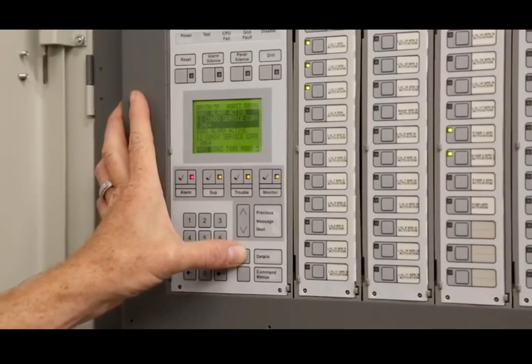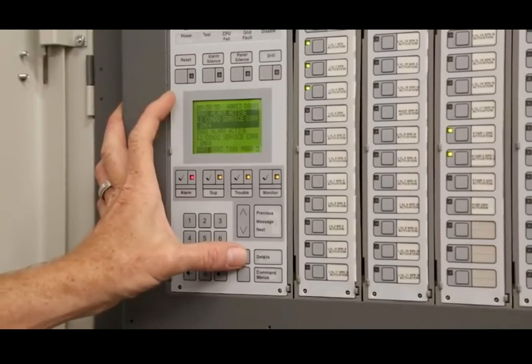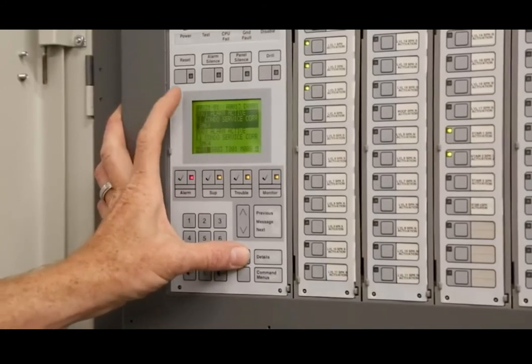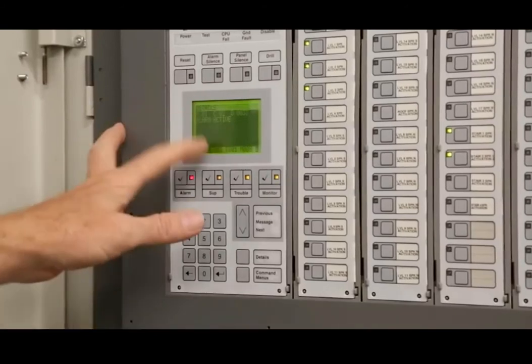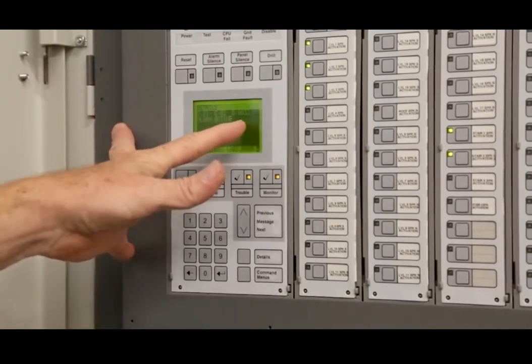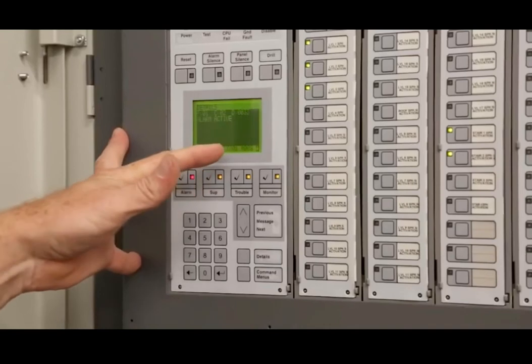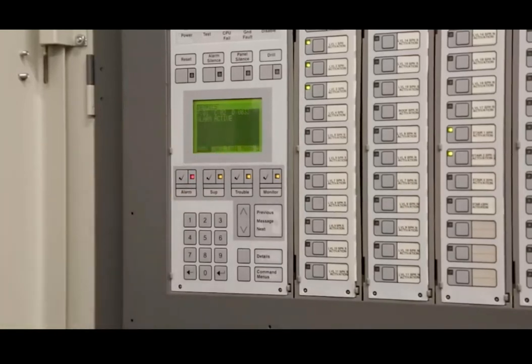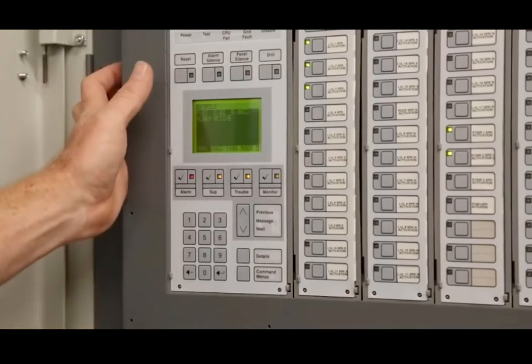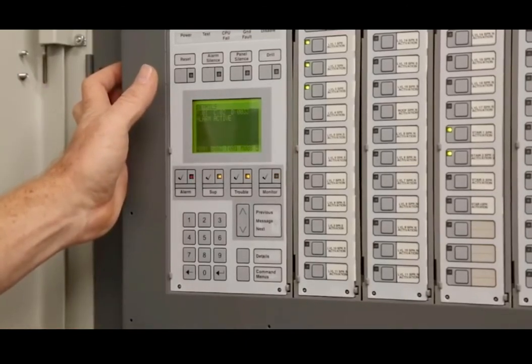If it's up higher and you can't actually see it and you see the number, remember I told you you can always go to details. Whatever's highlighted, we can go to that. So right now we know it's from panel 1, card 2, device 33. So to confirm it, you could go to that sticker, you look at it, it will flash red when it's an alarm. All right, and it flashes about every 10 seconds.